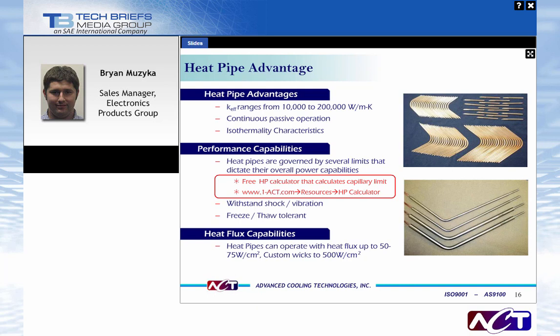Heat pipes are governed by several limitations. The biggest from a design perspective is the capillary limit, which is typically the first limit you'll hit in terrestrial systems. This is basically the wick's ability to overcome the various pressure drops in the system — the capillary pressure must be higher than your vapor pressure drop, liquid return pressure drop, and the pressure drop from gravity. When we design heat pipes, we look at the worst-case orientation and design accordingly. Tools available include the heat pipe calculator and a design guide for sizing and fitting heat pipes into your system.